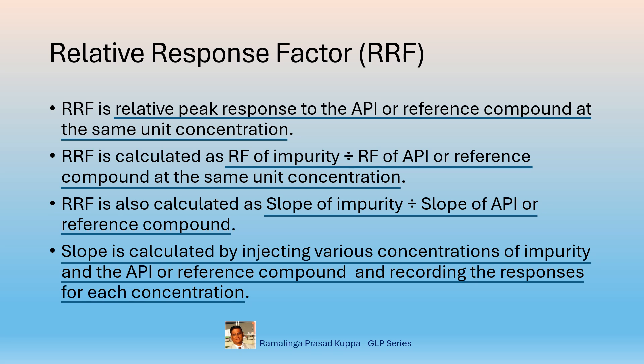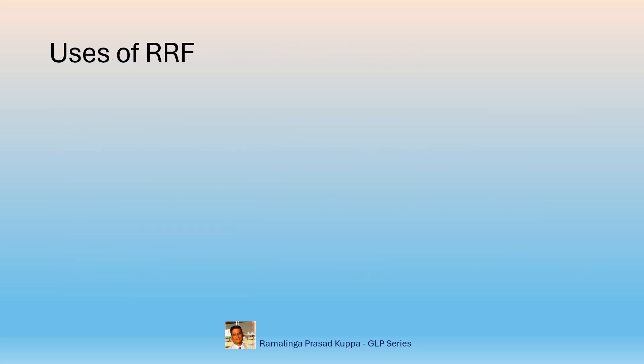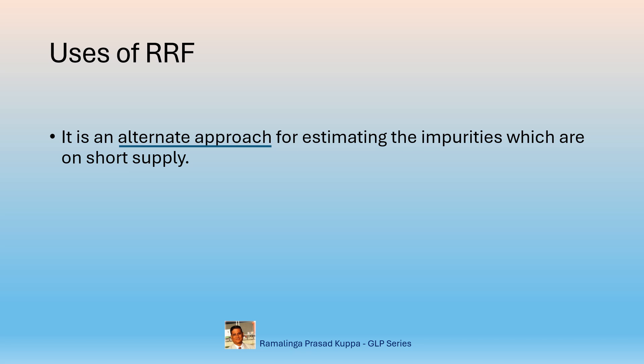Your robotic HPLC automatically provides information on slopes when programmed with RRF replicate injections, but it is important to understand exactly what the response factor and relative response factor mean. RRF is an alternate approach for estimating impurities for which impurity standards are in short supply. Sometimes there will be a shortage of impurities with authorized supply agencies, so the test method provides RRF for accurate estimation of the impurities.